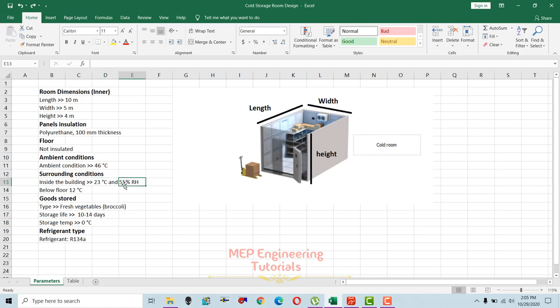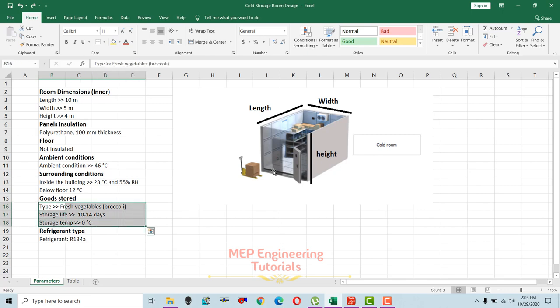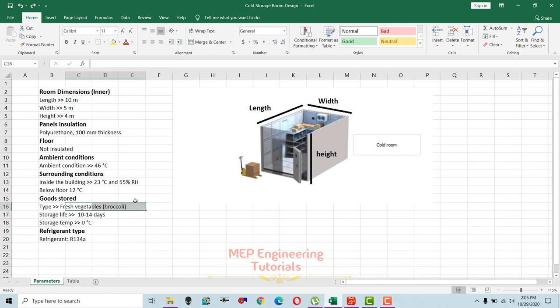The surrounding spaces temperature is 23 degrees Celsius, and humidity for thermal comfort is 50 to 60 percent, so we've taken 55 percent relative humidity. Below-floor temperature is kept at 12 degrees Celsius — normally we keep 10 to 12. The most important thing for cold storage room design is the goods: what type of goods you are going to store. In our case we are storing vegetables — specifically broccoli.